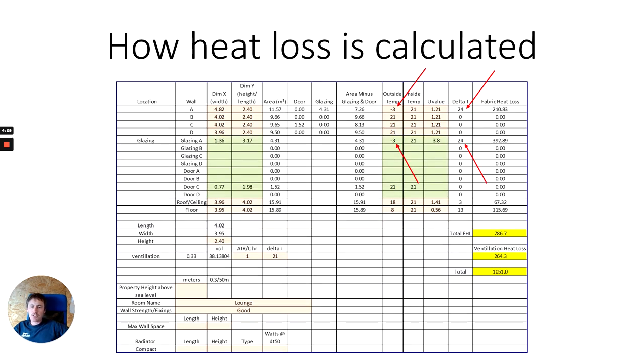On the heat loss survey shown here, only one wall is actually experiencing heat loss — the external wall. With an outside temperature of minus 3°C and a room temperature of 21°C, we have a 24-degree difference, multiplied by the square meterage and the U-value, giving us 210 watts of heat loss through that wall. Adding the window, floor, ceiling, and ventilation loss gives us the total heat loss for the room. One of these sheets is done per room, so there is quite a bit of measuring and work involved.